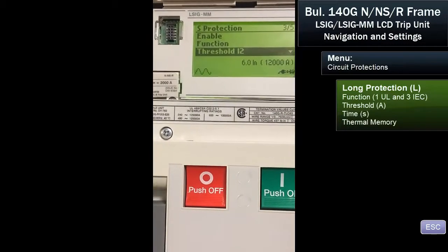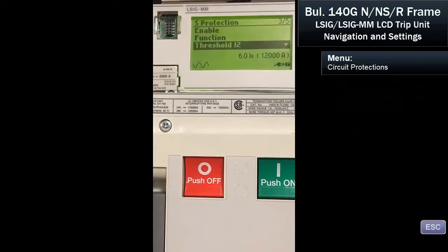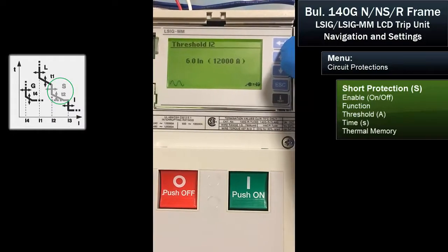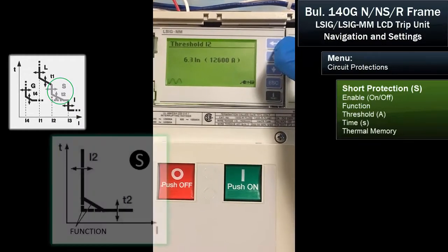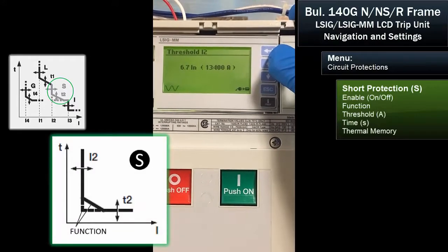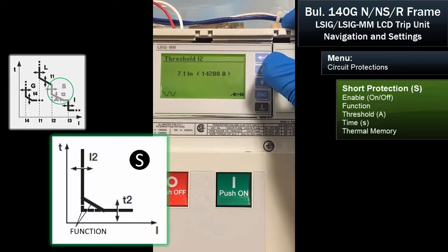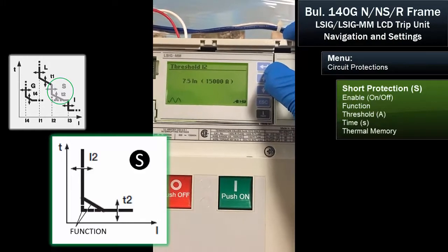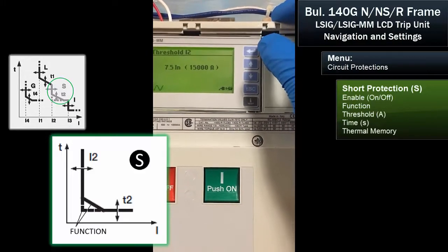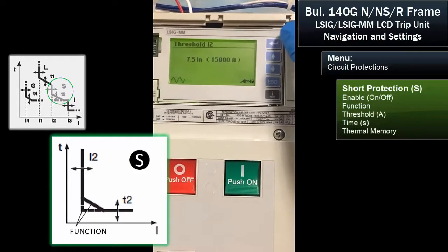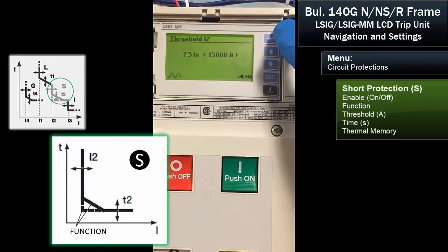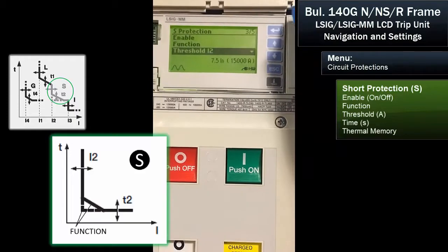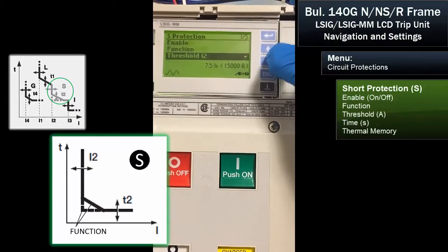We've set the long time. Now we're going to do the short time and the value of that. We hit the enter button — it's a multiple of the rating. We'll set that at seven and a half times, which will help define our time current curve. That's been saved.